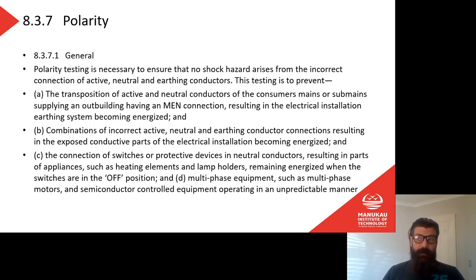It can be tricky to work out, I know this sounds crazy, but it can be tricky when you have a supply coming in from the street or power lines. It can be tricky to work out which one is phase and which one is neutral. Why? Because if I test between the two, it tells me there's 230 volts. If they weren't colored, how would I know which one is which? I can test it any way I like. I still only know it's 230 volts. So polarity testing needs to be done physically to earth.